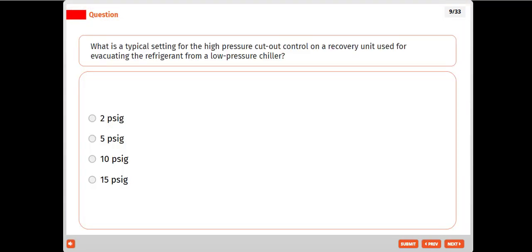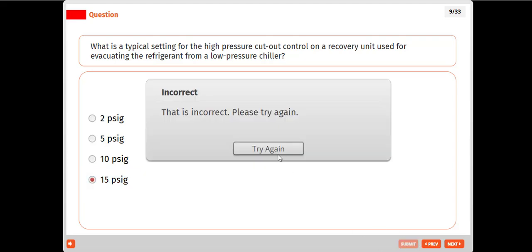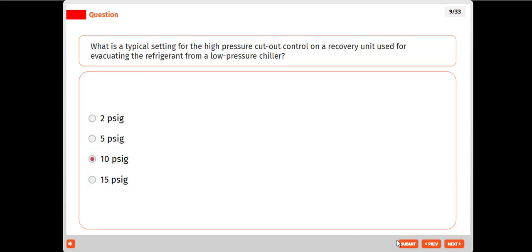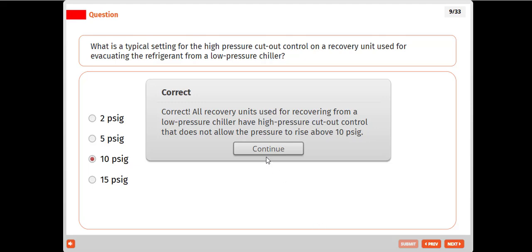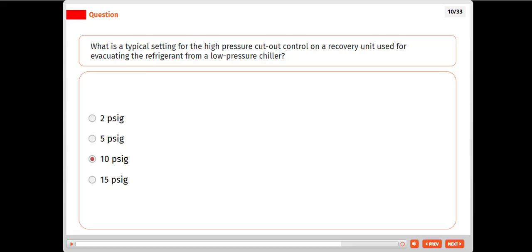What are the typical settings for the high pressure cutout control on a recovery unit used for evacuating the refrigerant from a low pressure chiller? Highest pressure is 15. Oh, 10? Yeah. All recovery units used for recovering from a low pressure chiller have a high pressure cutout control that does not allow the pressure to rise above 10.